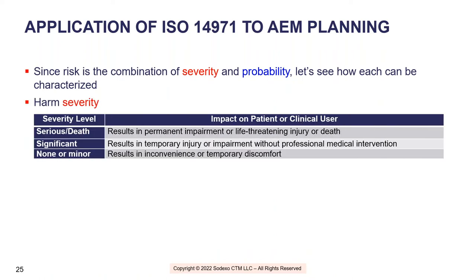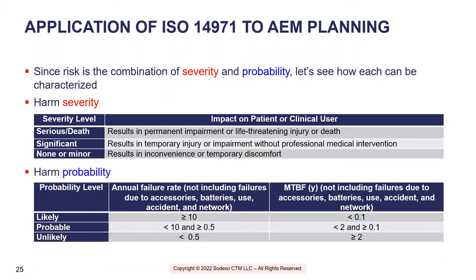So harm severity, we use a three-tier model: none or minor, significant or serious, and death. This is impacted patient or clinical user. And then the probability, again, likely, probable, unlikely. These are measured with either failure rates or mean time between failures, and these are true failure rates.